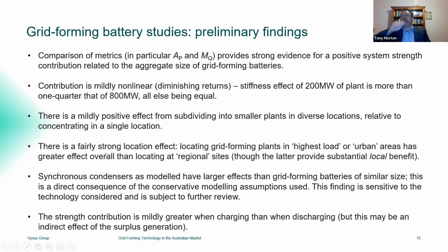We see a bit of a location effect as well, depending where we put those dispersed grid forming plants. When we put them in the parts of the network with the highest load, generally speaking, or if we put them in urban areas, we actually do get a slightly greater effect than if we put them in areas where there's not a lot going on in that particular part of the network. So considerations of location do make a bit of a difference. It's probably a secondary effect. We still get the system strength contribution no matter where we put it. But if we're looking at the most bang for buck in terms of the overall effect on customers, then putting the grid forming plant where the customers are is actually getting us the greatest effect.